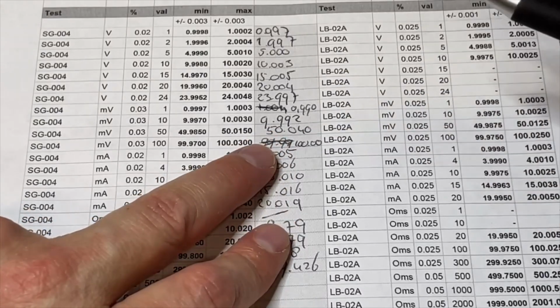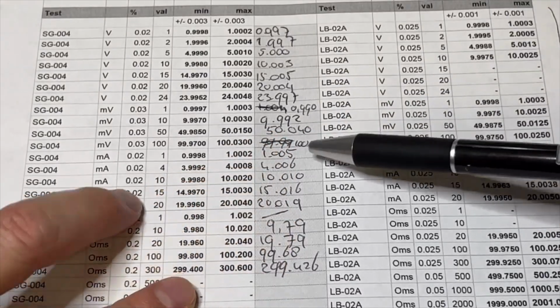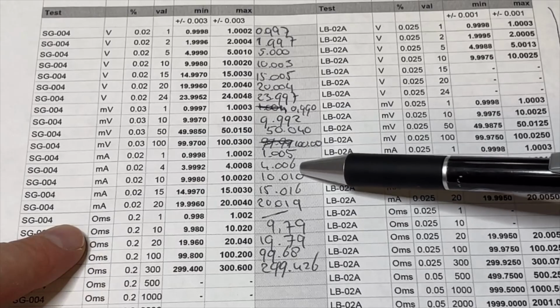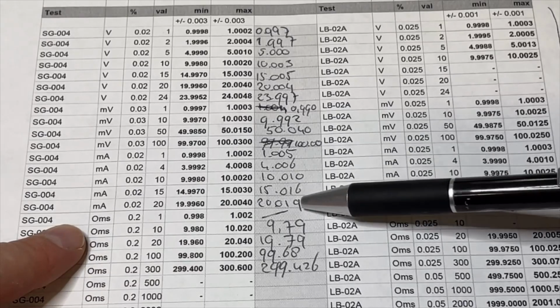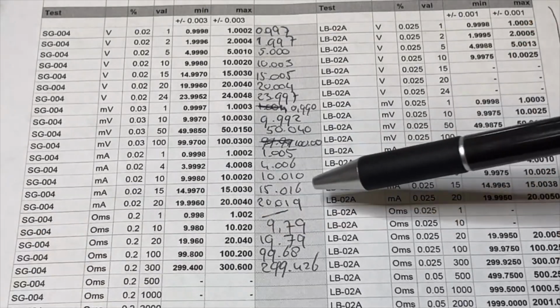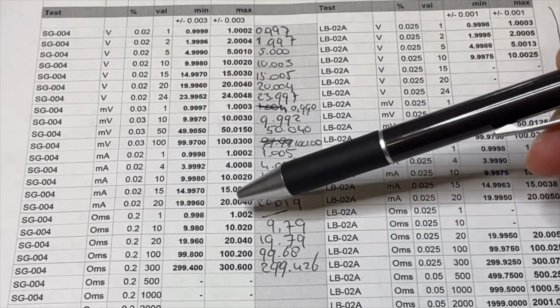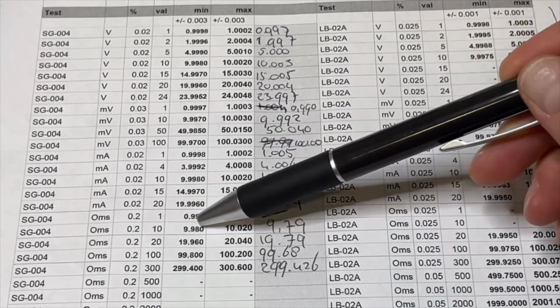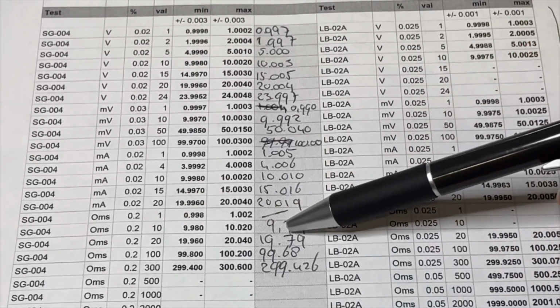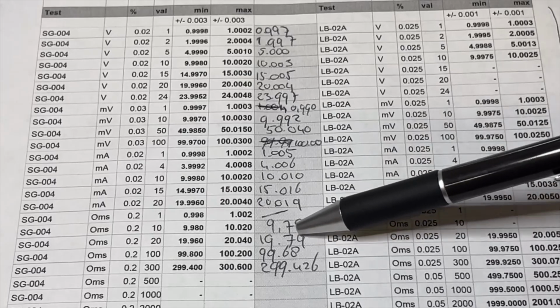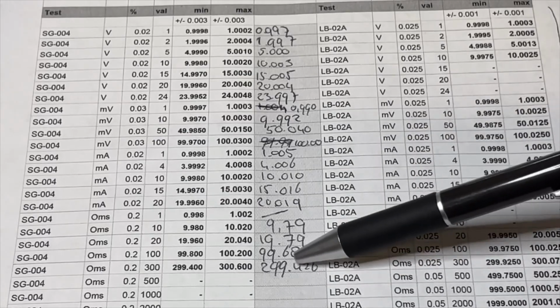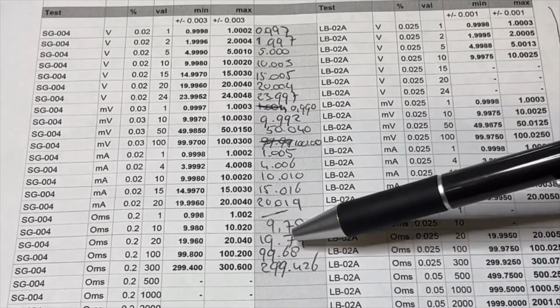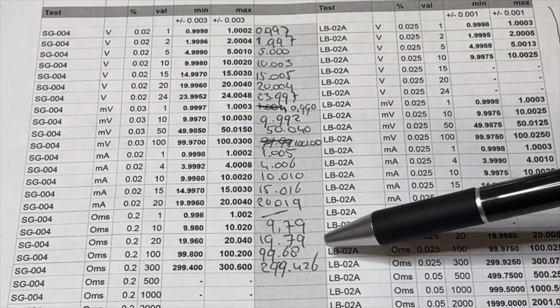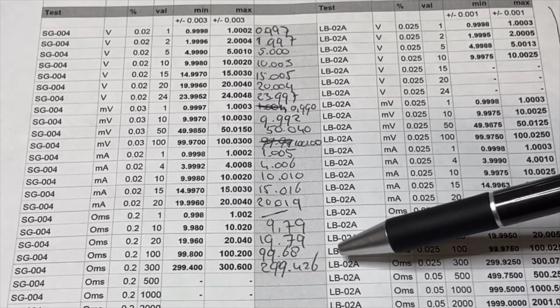Here it's correct, here it's correct. Then we have the milliamps - they were again very good. The resistance is also good. Look here, we have the 0.2, but here it is plus 1, so that makes it exact. We can get it a little bit higher with calibration, but the point is it is within specs out of the box. Here too, here too.